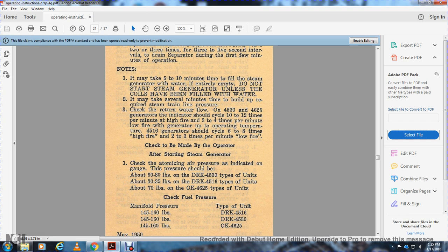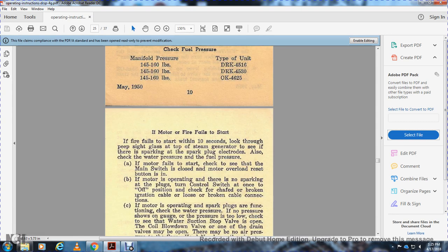Check the fuel oil manifold pressure: 145 to 165 pounds for the DRK 4516, 145 to 160 pounds for the DRK 4530, and 145 to 160 for the OK 4625. If the fire fails to start within 10 seconds, look through the sight glass at the top of the generator. See if there is a spark at the spark plug with the electrodes offset, and check the water pressure and fuel pressure if the motors fail to start.